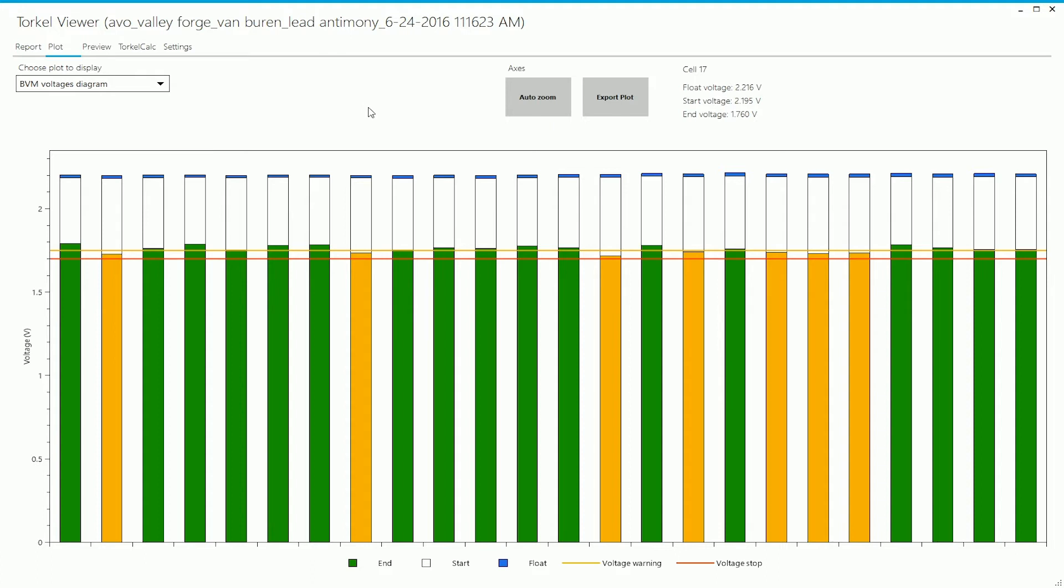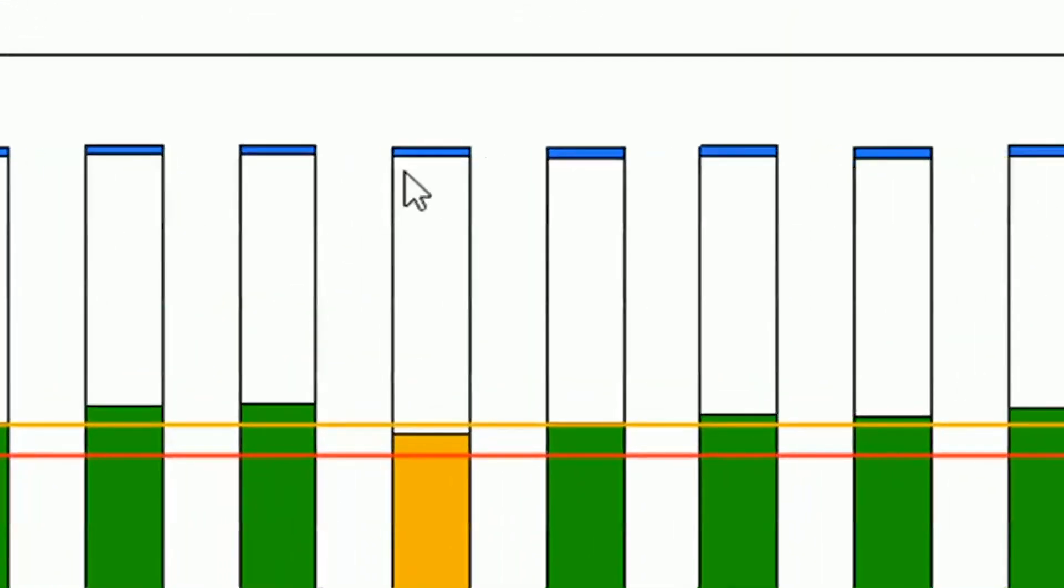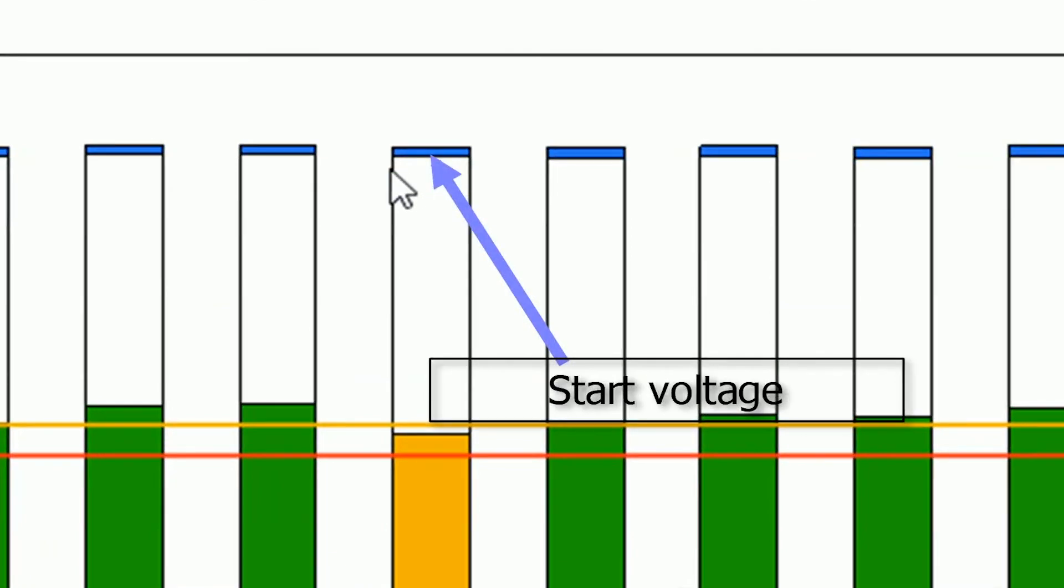You see the end voltage, you see the start voltage, and you see the float voltage. The legend here shows you how to interpret the bar graphs. So the upper end of the white bar corresponds to the start voltage for that particular cell.